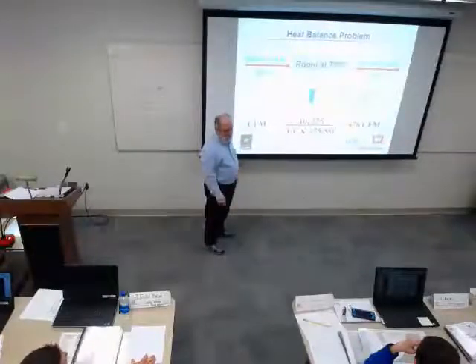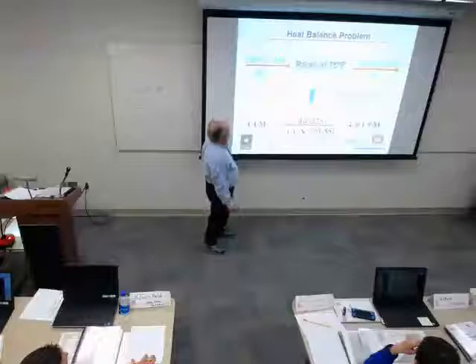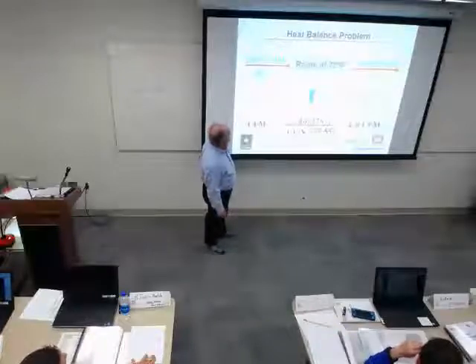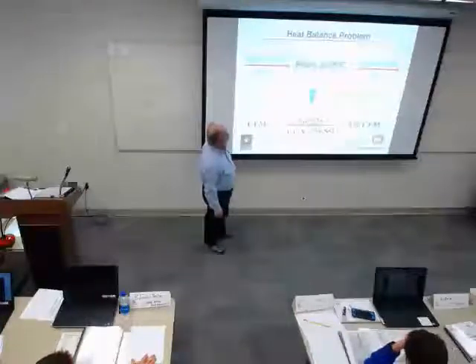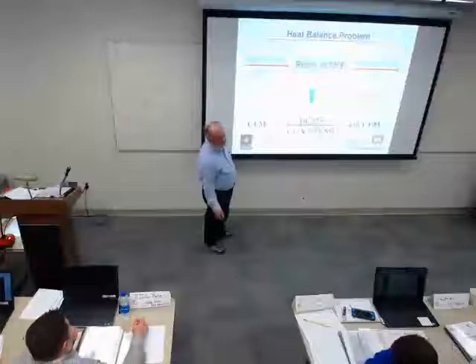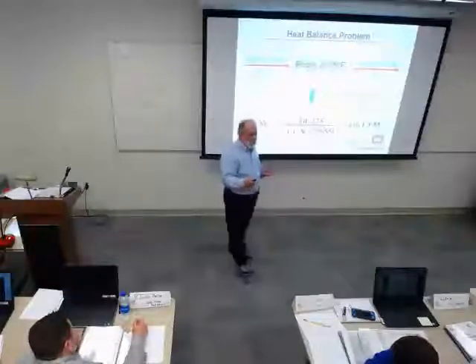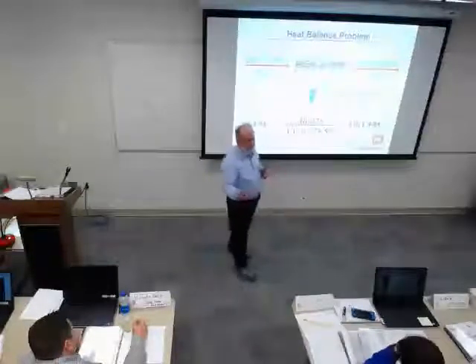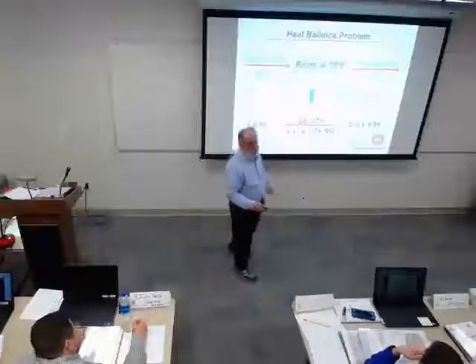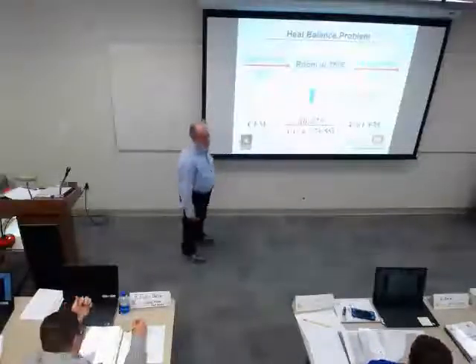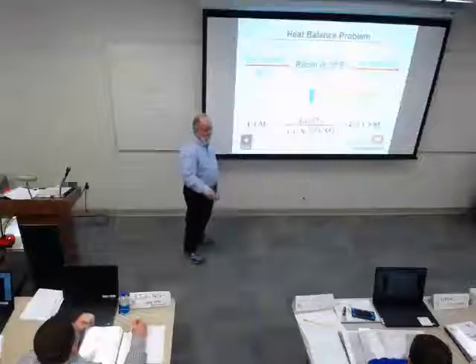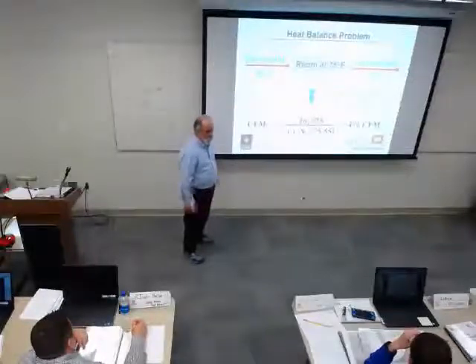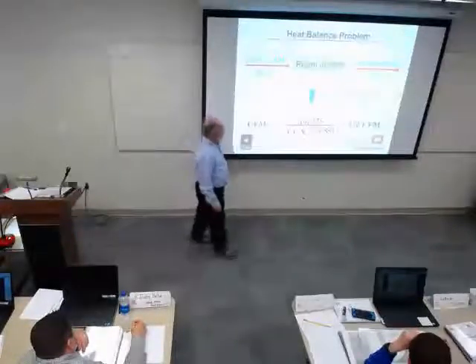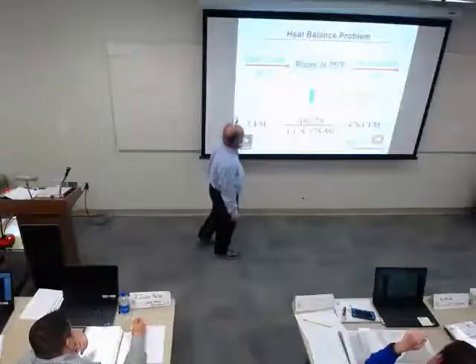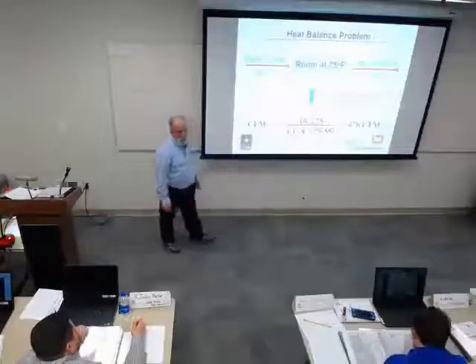Why is it 1.1 instead of 1.08? In this case, they decided that 55 degrees was dense enough to use that 1.1. If you're working with this quite a bit, you play around with it and come up with your own factors for different temperatures, really. But if you don't, just grab one of those two. You're not going to be greatly off because it's 0.02, it's not a big number. Because we're at 55, which is kind of on the low end, we chose the 1.1 instead of 1.08.